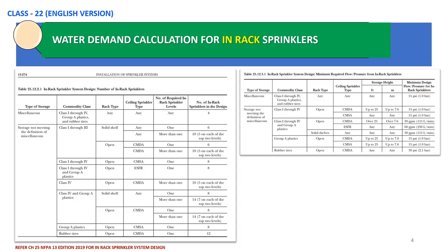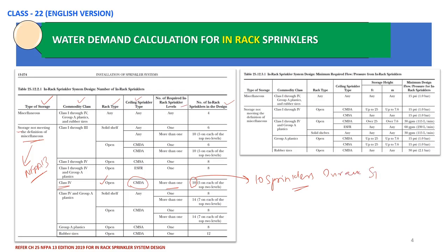The type of storage is storage not meeting the definition of miscellaneous — you can check NFPA 13 definitions for that. In our case, the commodity class is Class 4 and the rack type is open type racks. Ceiling CMDA sprinklers are already installed per project requirements. The number of required in-rack sprinkler levels is more than one, and the number of rack sprinklers in the design — this is very important — will be 10.